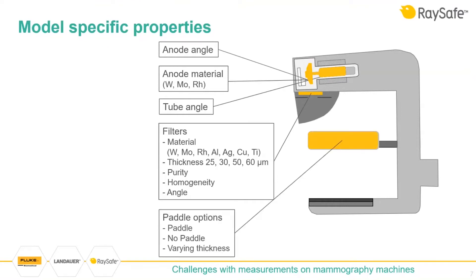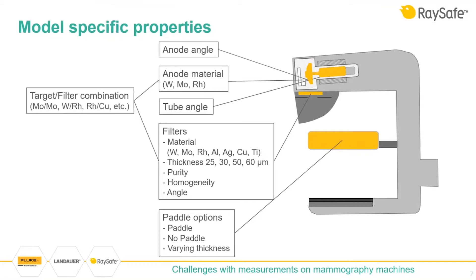Filters can also be placed at different angles between machines. On top of this, we have the compression paddle, which can be present or absent, and on one and the same machine you can have nine or ten different paddles that all have different thicknesses. These variations add significantly to the complexity of these measurements.